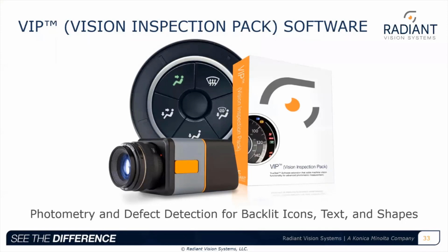Radiant's VIP software solution combines an imaging colorimeter or photometer for accurate and efficient photometric measurement with automated visual inspection software featuring the VIP license for registration and defect detection of unique backlit areas.